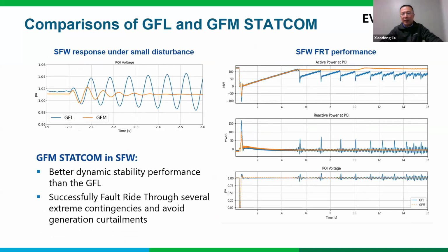This slide will compare the stability performance between the grid forming and the grid following STATCOM. The first diagram here shows the line outage scenario, where the grid is super weak. When there are disturbances from the grid and the short circuit capacity is slightly reduced a little bit more, the wind farm becomes unstable under the grid following control of the STATCOM. You can see that the wind farm becomes uncontrolled, with growing oscillations, right? The grid forming STATCOM instead can effectively make the system stable. This showed better small signal stability performance of grid forming over the grid following, right?